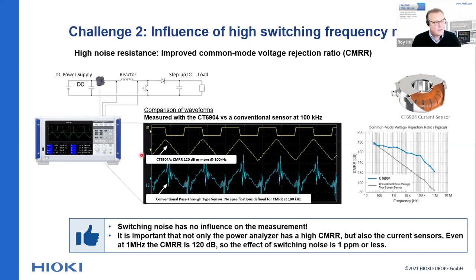Due to this hard switching of the semiconductor, there will be high frequency interference at the frequency of 100 kilohertz and its harmonics. And when we look at the current measurement through the reactor, we see here at the bottom, where we use an ordinary current sensor, that all this frequency interference, so the switching noise which is created by switching the semiconductor, is measured by this current sensor. And this is, of course, not a good solution to measure your power accurately. There is, however, a solution. As you can see here, the yellow trace, E1.